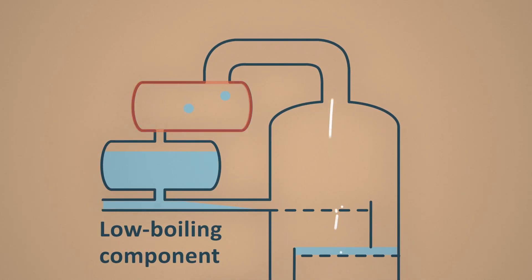For this purpose, the reflux exchanger condenses the vapor at the top of the tower. The condensed liquid accumulates in the reflux tank and enters the top tray as a reflux. The required temperature mode is obtained in the fractionator by adjusting the flow rate of steam stripping and refluxing. That ensures that the final product gets the commercial quality.